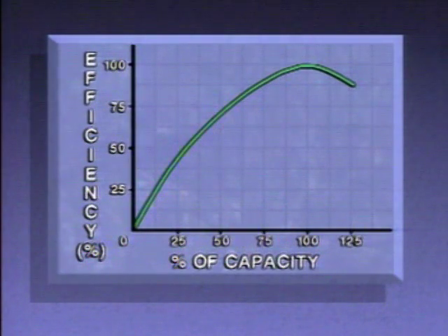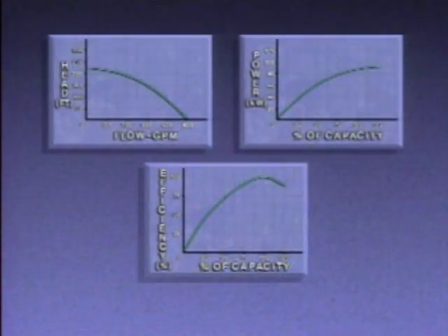If the other plant concerns, such as safety and production, allow it, this is the most desirable flow rate at which to operate this pump. Pump curves are often provided by manufacturers to help describe how pumps are supposed to perform. By comparing actual data from a pump with the information provided by the curves, a pump's performance can be determined.